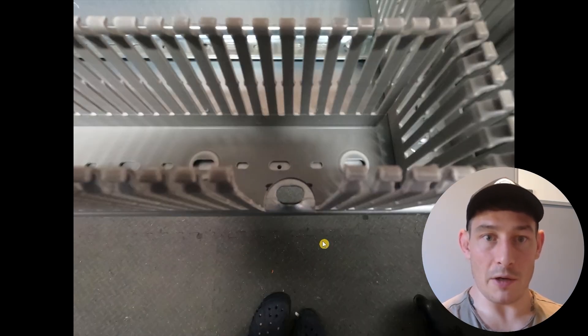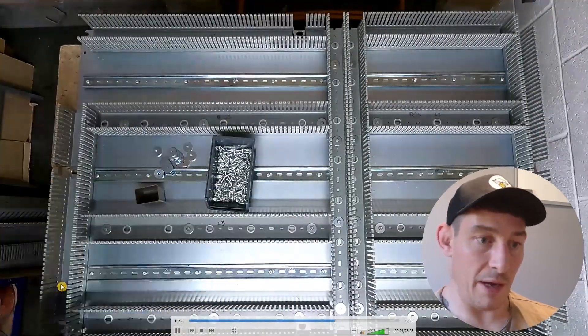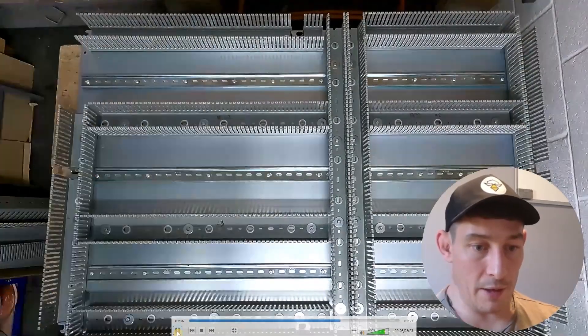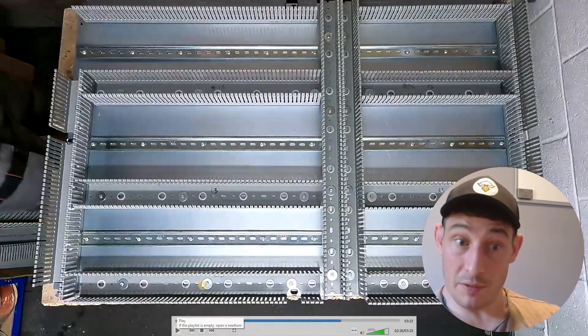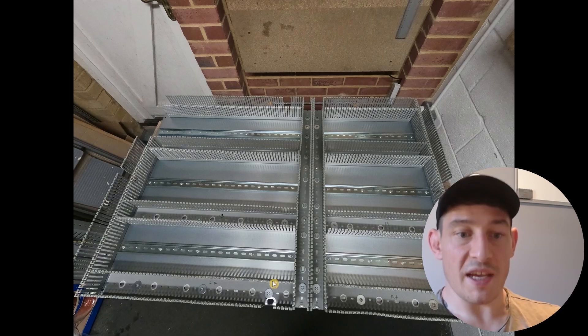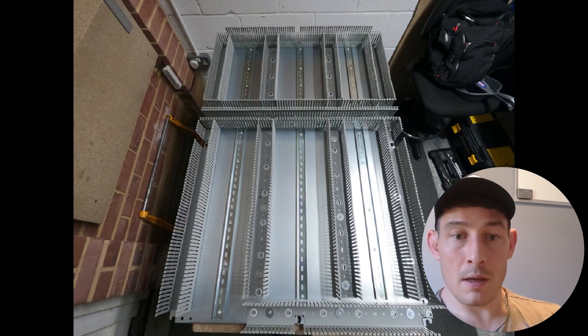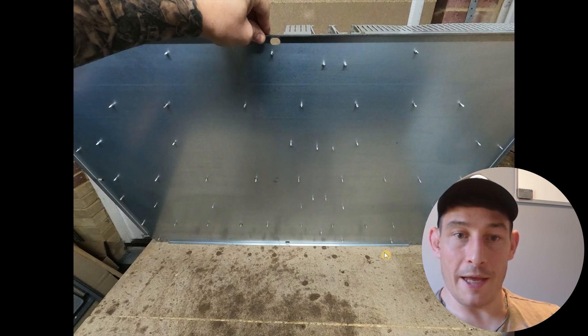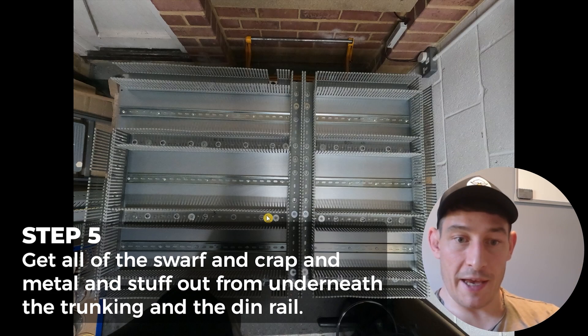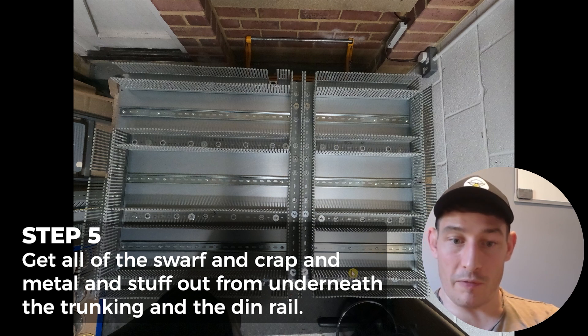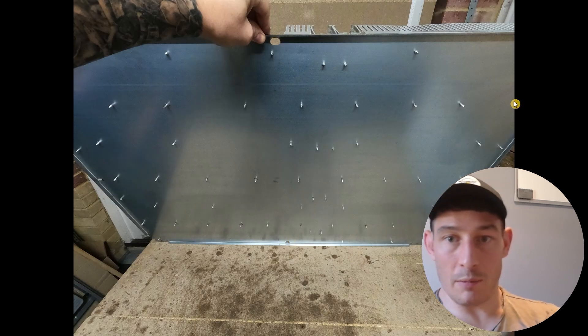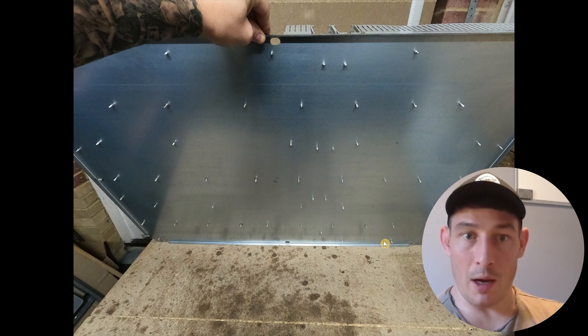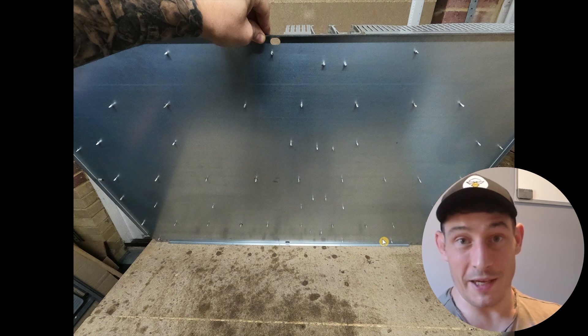So now just fixing those final bits of trunking around the edge, and then by this point everything's still loose. So you'll see just then that I tipped up the back plate. And then what I'll do is I'll put it on its side like that, move it about a bit, and what I'm trying to do is get all of the swarf and crap and metal and stuff out from underneath the trunking and the DIN rail. So I might do it on this side, I might do it on this edge, and just try and free up all that crap underneath the trunking and DIN rail before fixing it for good.